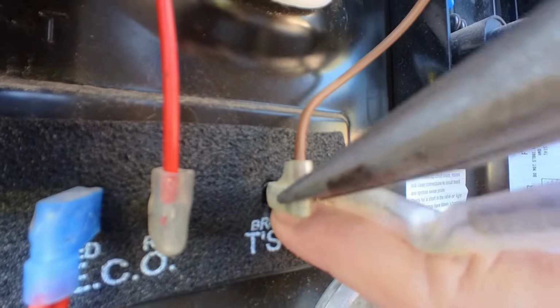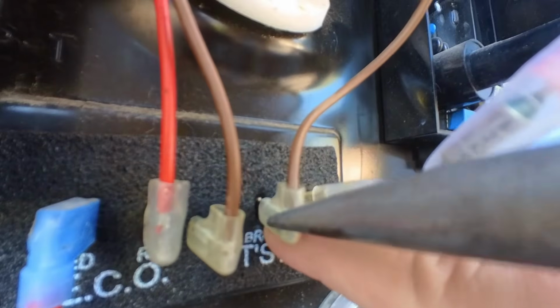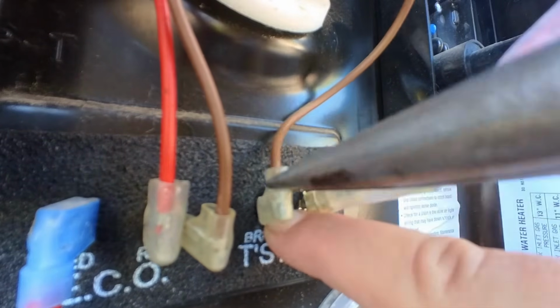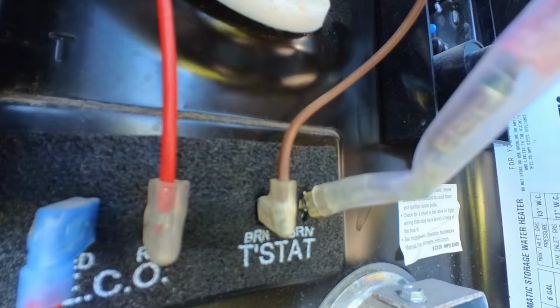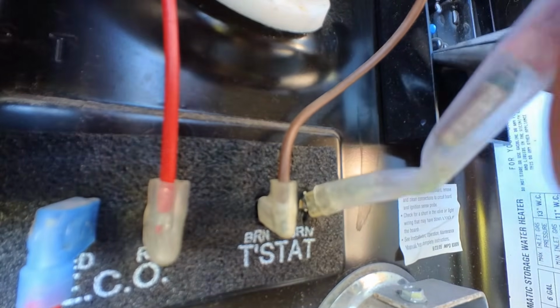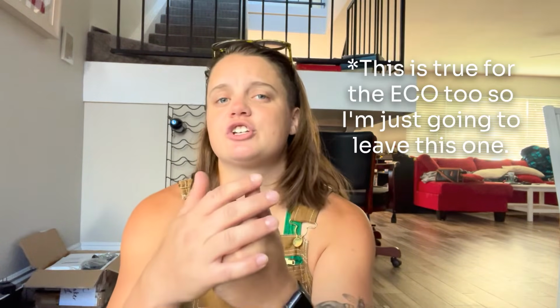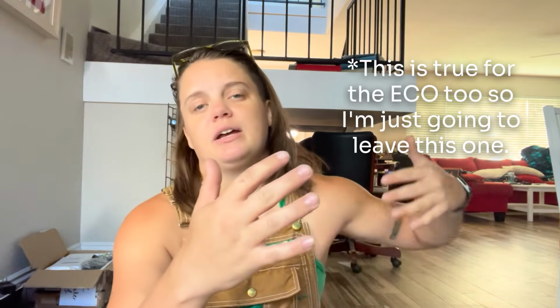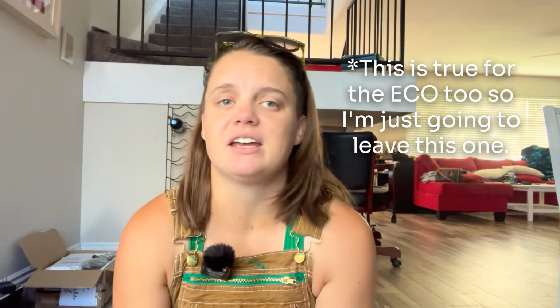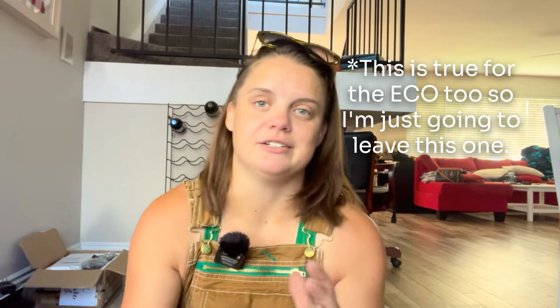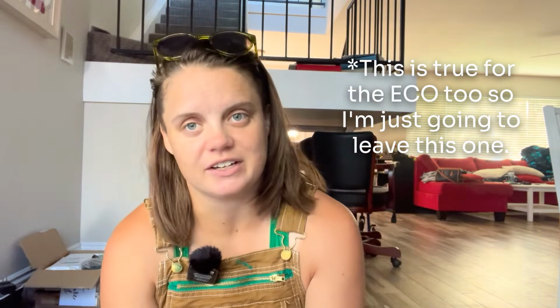If and when you do this, take a finger and put it right on the T-stat in between the two probes. It's not going to shock you, you're good. Support the T-stat as you're pulling back on that terminal with some needle nose pliers. There's a spring mechanism behind the ECO, and if we just start tugging on the terminals, that spring can pull back and smack into the tank, hurting itself and causing more problems than we're fixing. So let's not do that. Support it with a finger, and pull back on the terminal carefully with the needle nose.